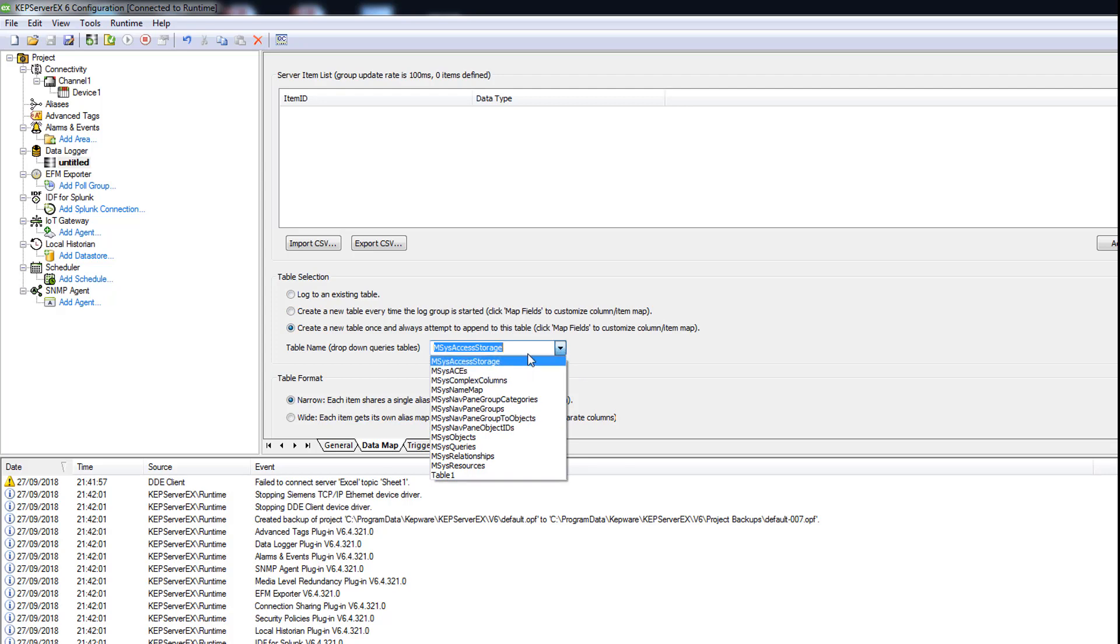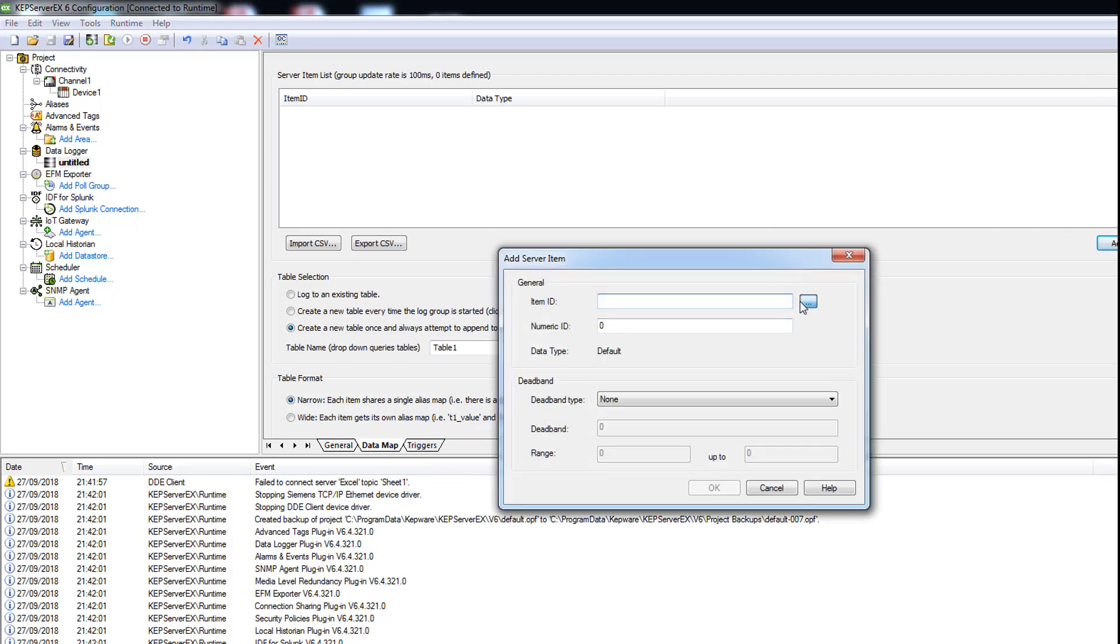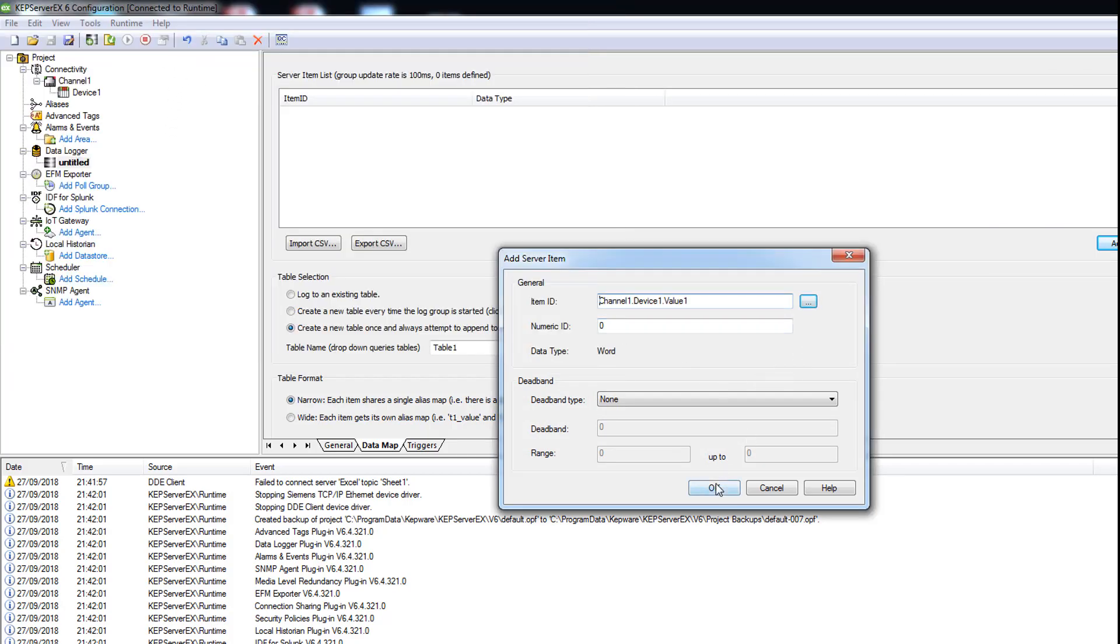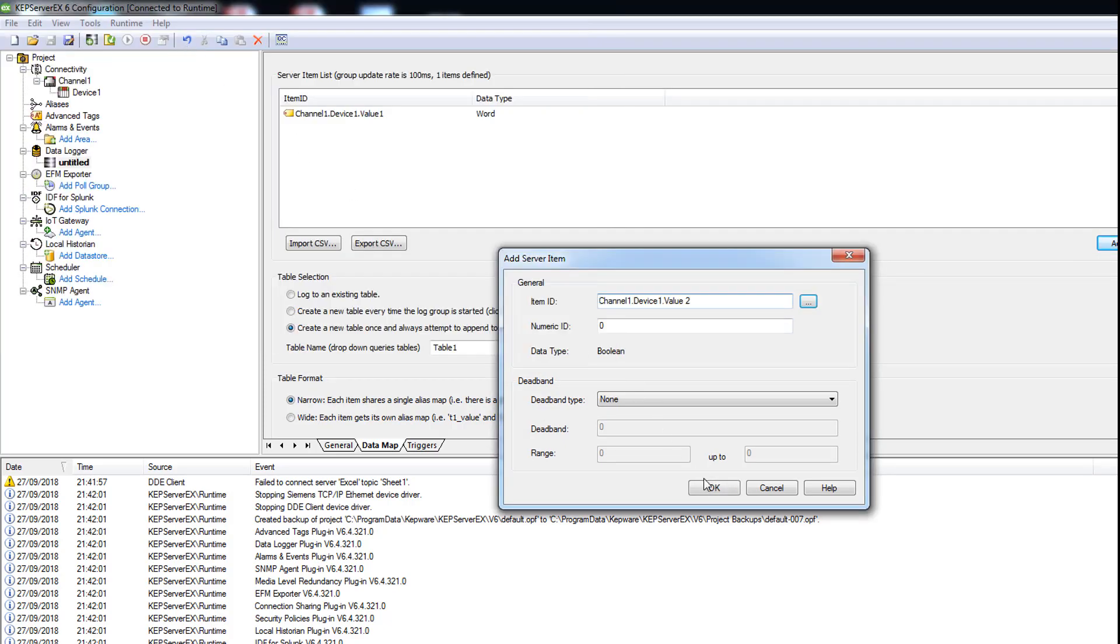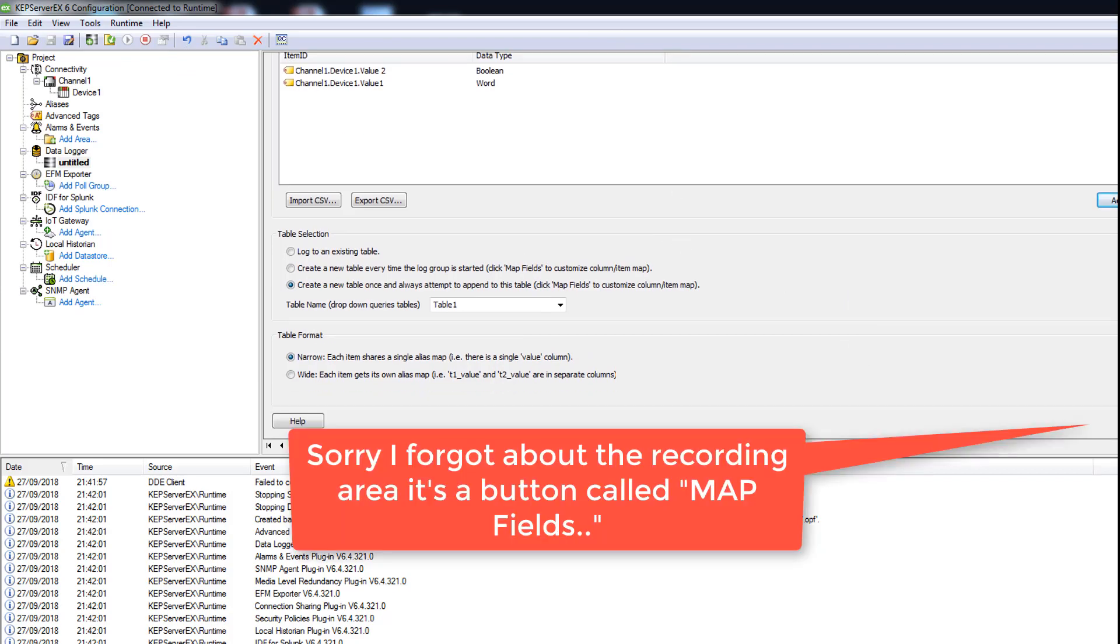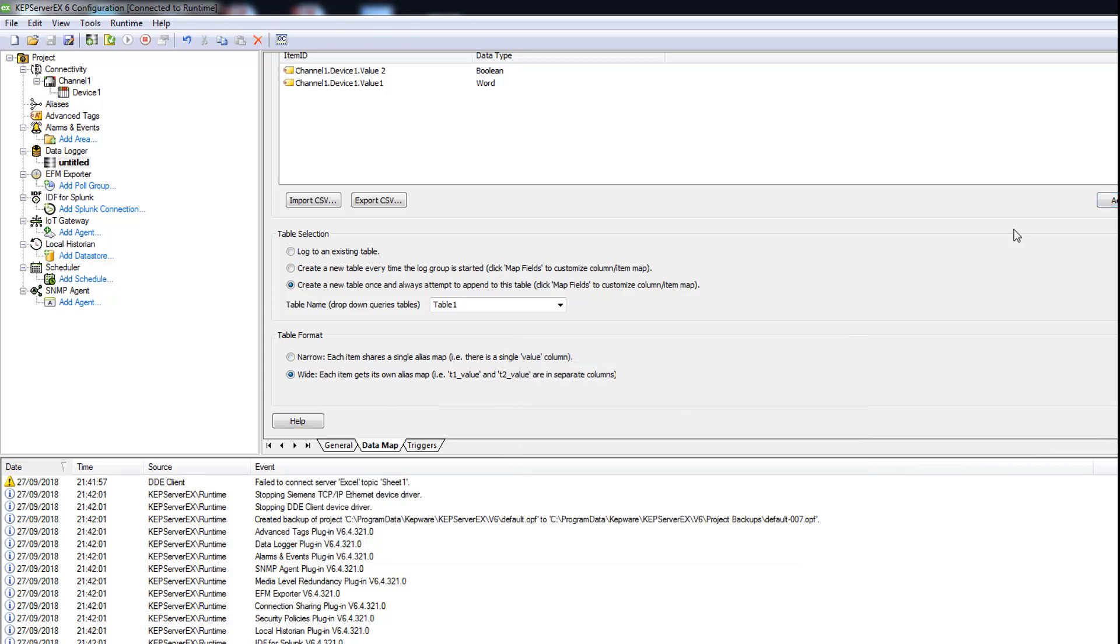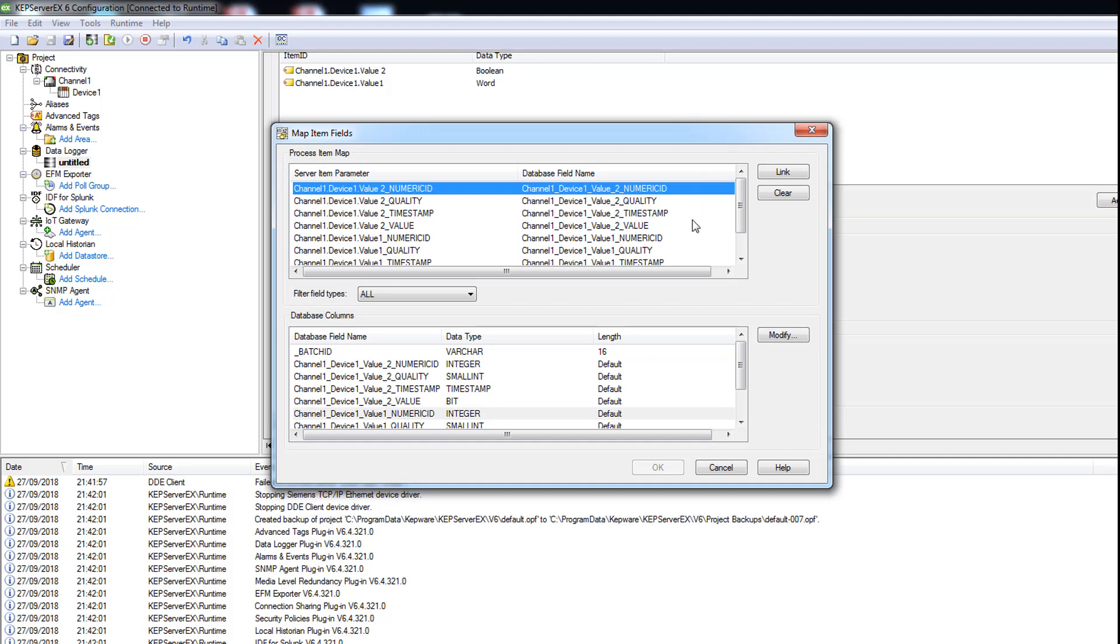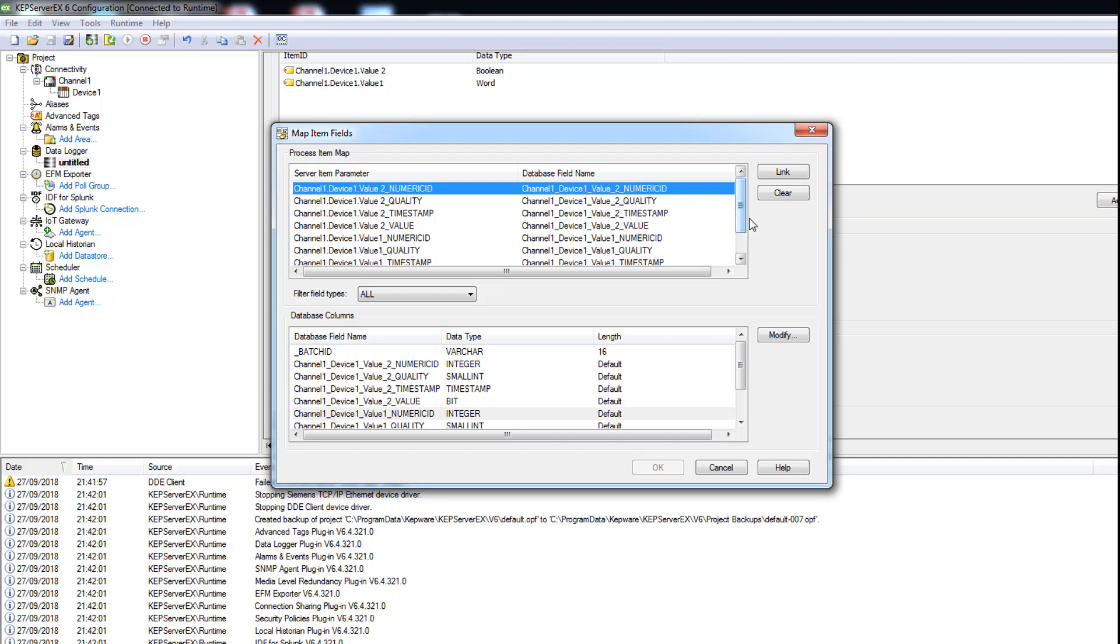And you go to the data map, check create a new table once and only, and you select your table that you created just right now, it's table one. You add your two tags, add like value one and value two. Here you go to table format, we use each item gets its own column. We add the map field. Here you can add what you want to show. Every tag has its value, timestamp, quality, and numeric ID. I let it just the value for now.